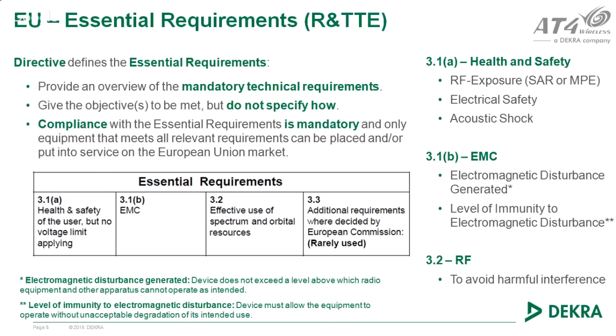They say, for instance, that a device must be safe according to electrical safety and acoustic shock. The radio frequency exposure for persons cannot cause any damage, and it must be compliant with EMC, in terms that it does not generate disturbance to other devices over some limits, or it might be ready to accept some disturbance from other devices, okay? And in terms of radio frequency, it uses the spectrum correctly. It transmits in the band that is assigned to the device. For instance, a Bluetooth device transmits in the 2.4 gigahertz band, and emissions out of these bands are below the maximum limits, okay?